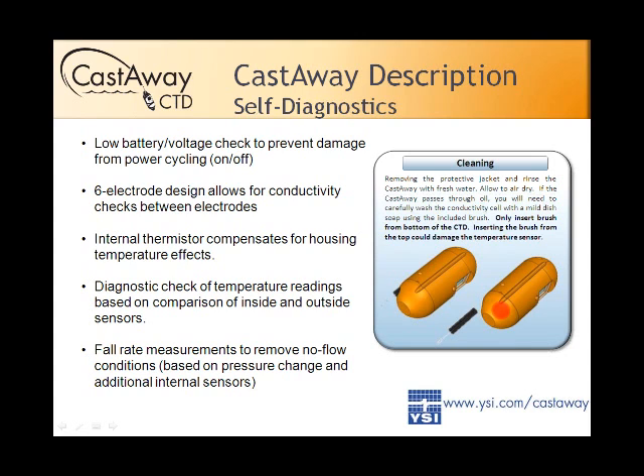The Gulf Coast work involved going through oil. The system will continue to function once it's cleaned. If it goes through oil and those sensors get coated, it can interfere with your measurement. All you need to do when you recover it — even out in the field — is run that bottle brush up and down to clean those sensors off. We also have self-diagnostics where the system will detect if the electrodes are coated in an inconsistent way that could affect your measurement and warn the user to consider cleaning.